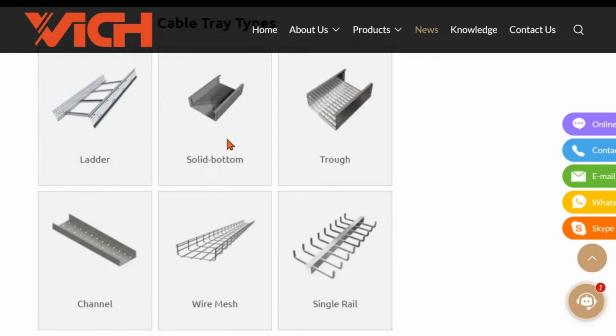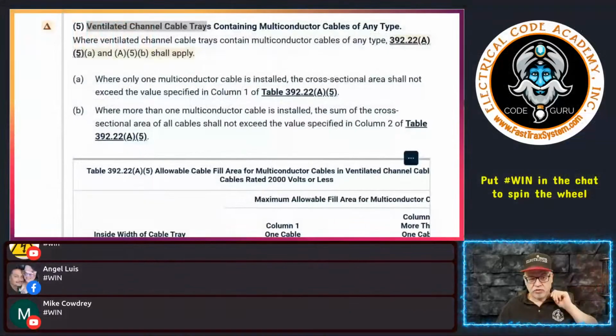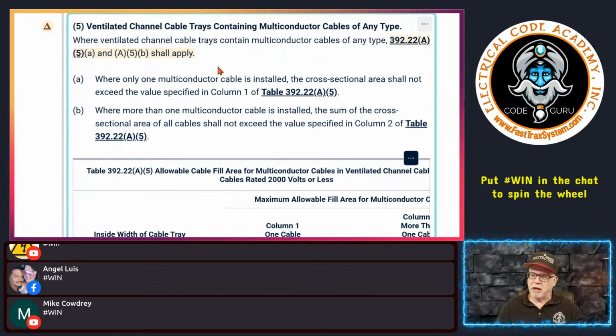The most predominant we see are ladder and perforated or ventilated trough, okay? That's what we probably see the most. So just to put that mental picture in there, the different things that we're talking about, okay? All right, so if you do have what's called a ventilated channel cable tray, then it says where ventilated channel cable trays contain multi-conductor cables, any type can go in there, not specific to anything.